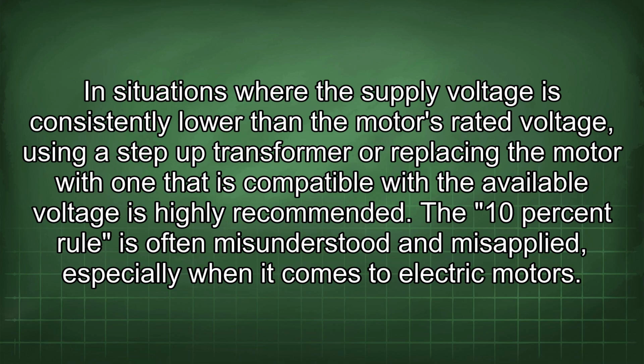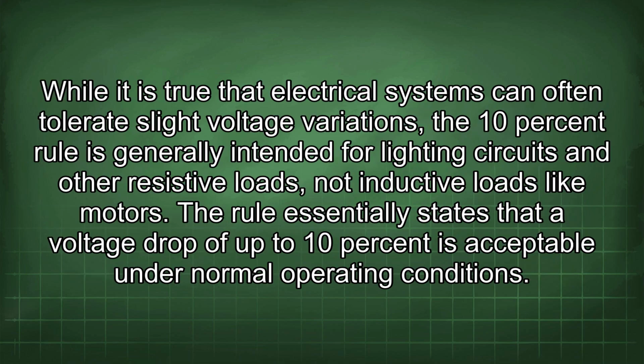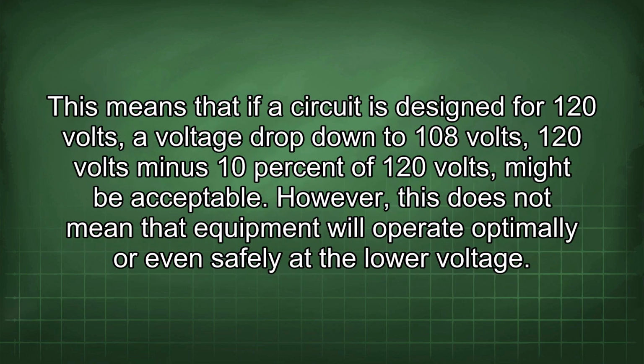The 10% rule is often misunderstood and misapplied, especially when it comes to electric motors. While it is true that electrical systems can often tolerate slight voltage variations, the 10% rule is generally intended for lighting circuits and other resistive loads, not inductive loads like motors. The rule essentially states that a voltage drop of up to 10% is acceptable under normal operating conditions. This means that if a circuit is designed for 120 volts, a voltage drop down to 108 volts, 120 volts minus 10% of 120 volts, might be acceptable.